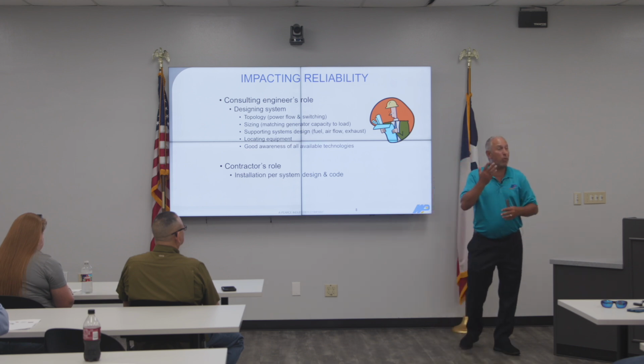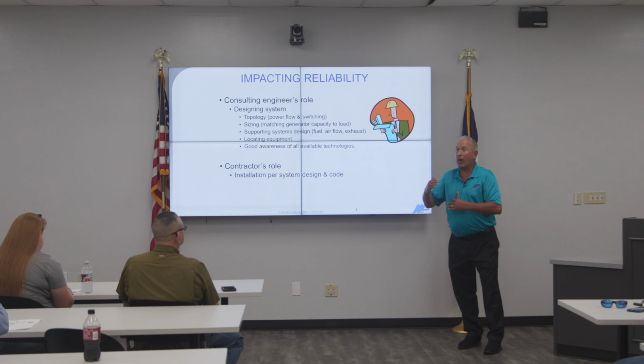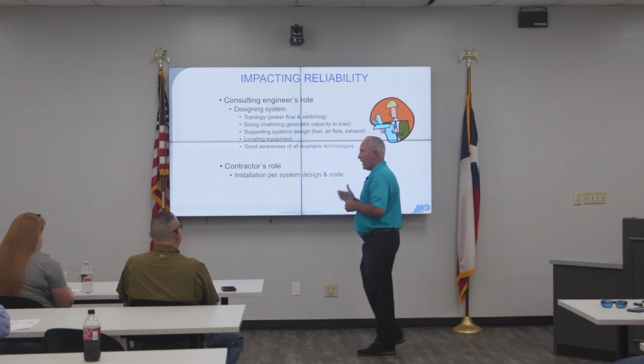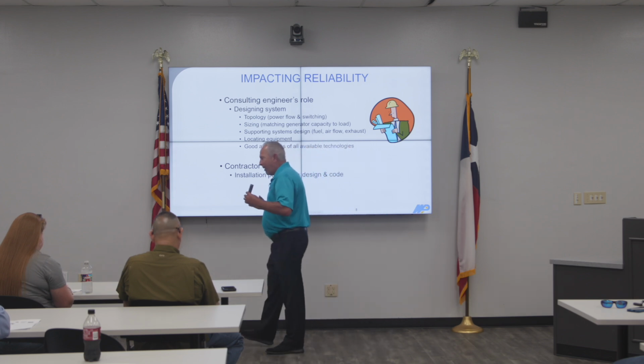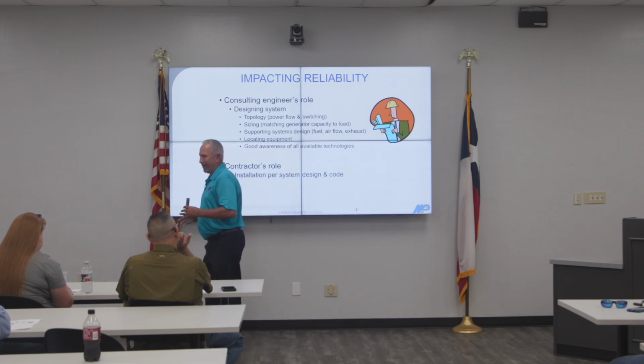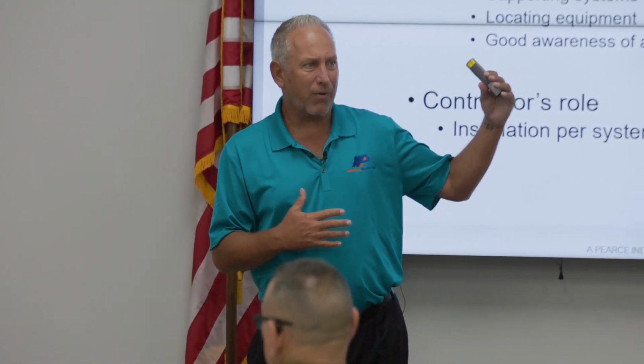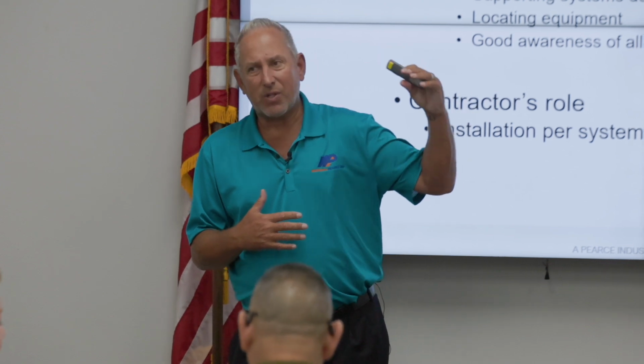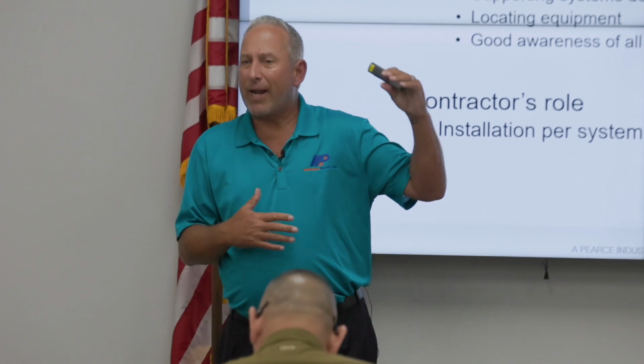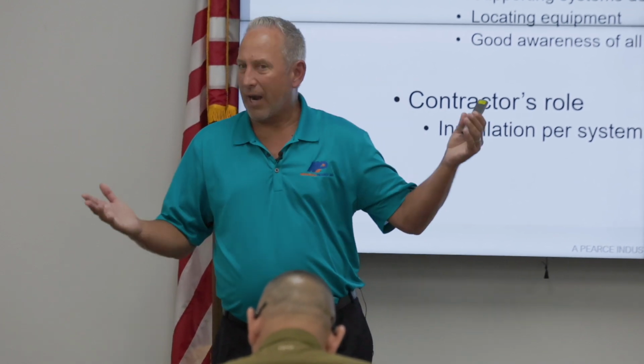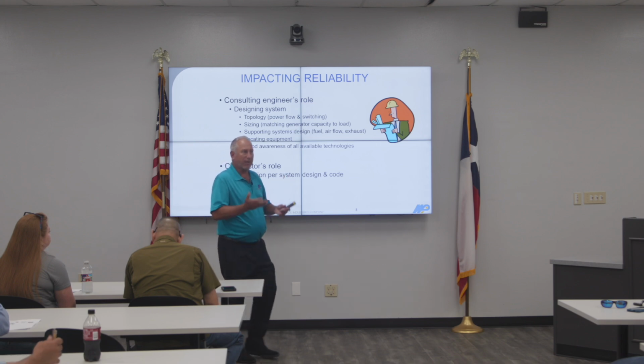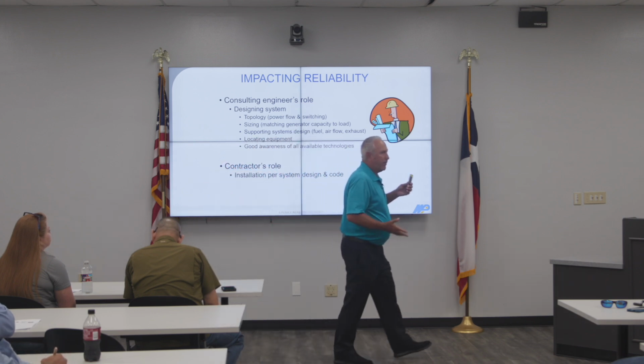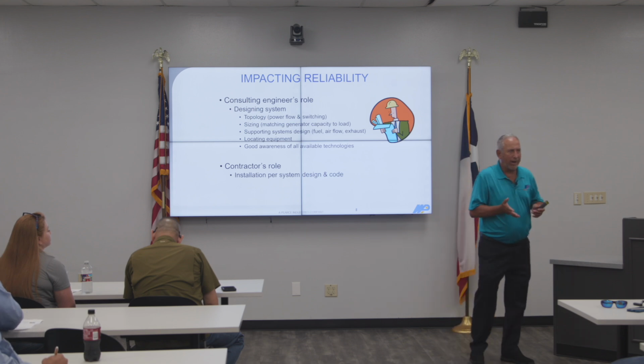When he's looking at your load profiles, we're trying to get that generator zeroed in. The tricky part, which we'll go into more later in this course, is the generator needs to be sized right. You're not doing me any favors by buying too much generator. The generator is designed to run with load on it, so if you don't have enough load on it, it's not going to operate the way it's supposed to. It's that tricky business of not overbuying, but zeroing in on the right product.